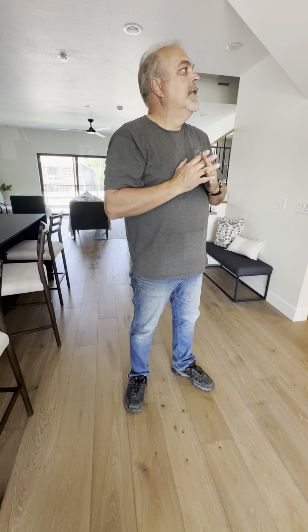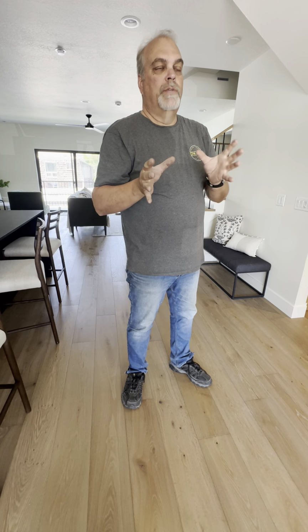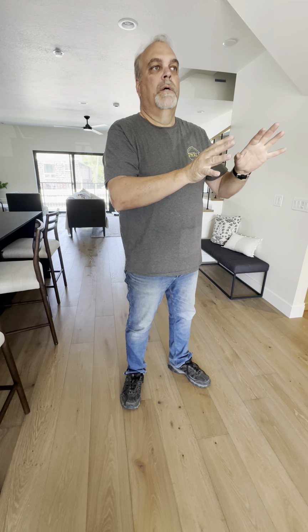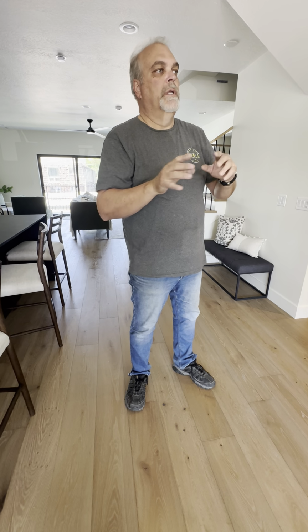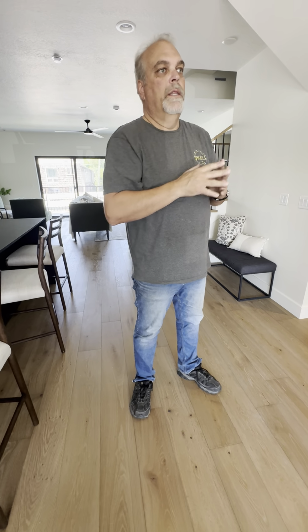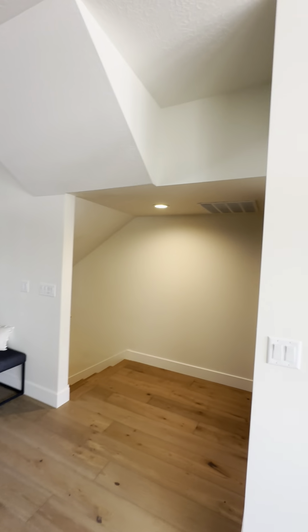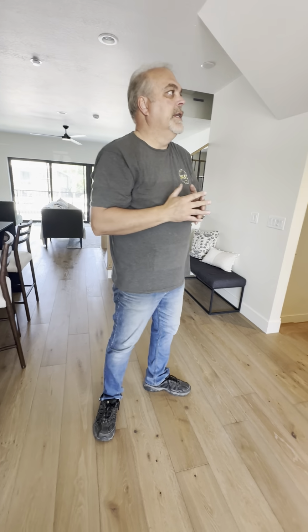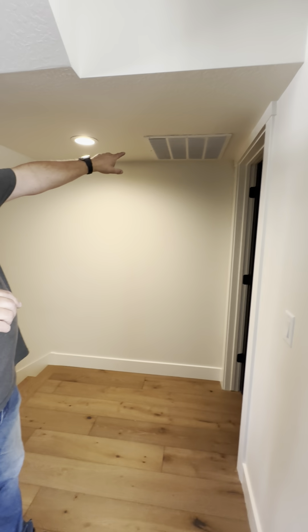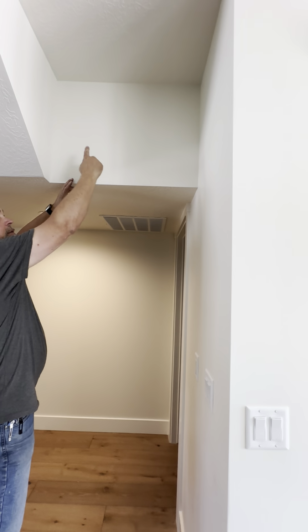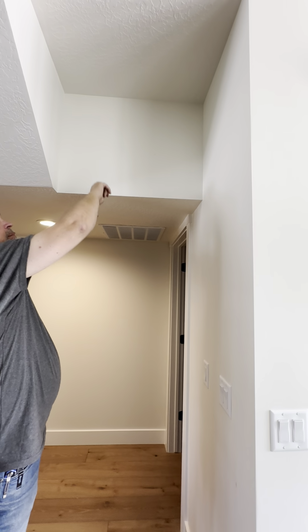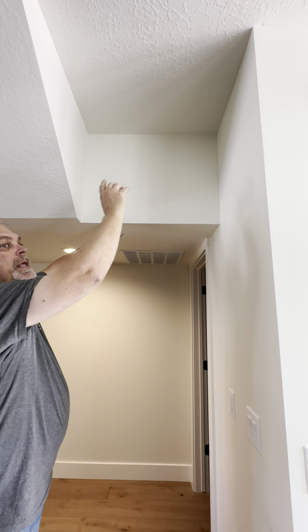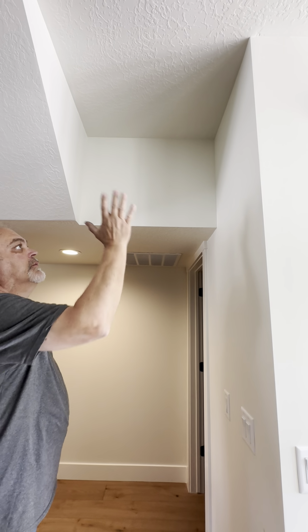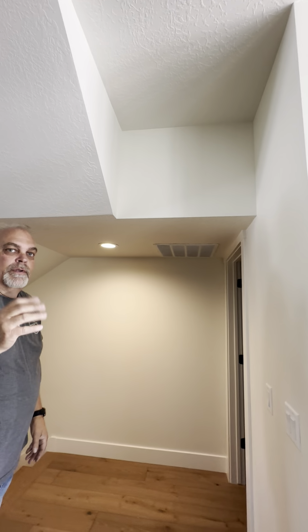So my solution to that, and there's a major design flaw here, but to work within the parameters that we have, which should solve a large part of it, probably not 100%, but a large part of it, is we remove the ductwork and reconfigure that, and this is just on the return air. We're going to put fiberglass duct in, and then come up and replace the duct going across with fiberglass, because that pulls a lot of that sound out of that airflow, and the fan itself is what we're hearing. Now the other idea is we're going to eliminate this, and we're going to bring fiberglass duct out to the front of this and then build this area out so that we can then build a configuration within this cavity that will give more distance basically between the return air and the ductwork. So that's what we have in mind.